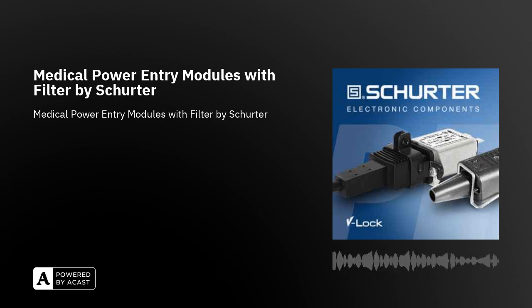The requirement for water protection is IP21, which is required for all medical home care equipment. Other medical applications may require even higher protection. Solution provided by Schurter is power entry modules with protection against ingress of water. 5707 with IP65 between PEM and device box and IP54 for connected power cord with V-lock. DG11, DG12 with IP65 between PEM and device box and IP54 for connected power cord with V-lock.